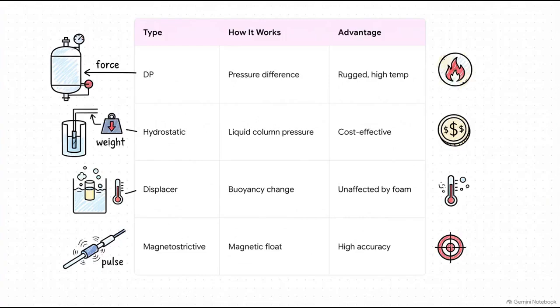So this first family relies entirely on physical contact and force. You've got your differential pressure, or DP transmitters, which measure the pressure difference between the top and bottom of a closed tank. Super rugged, great for high heat. Then there are hydrostatic sensors. These are beautifully simple, often dropped right into water wells. They just calculate the weight or pressure of the liquid column sitting right above them.